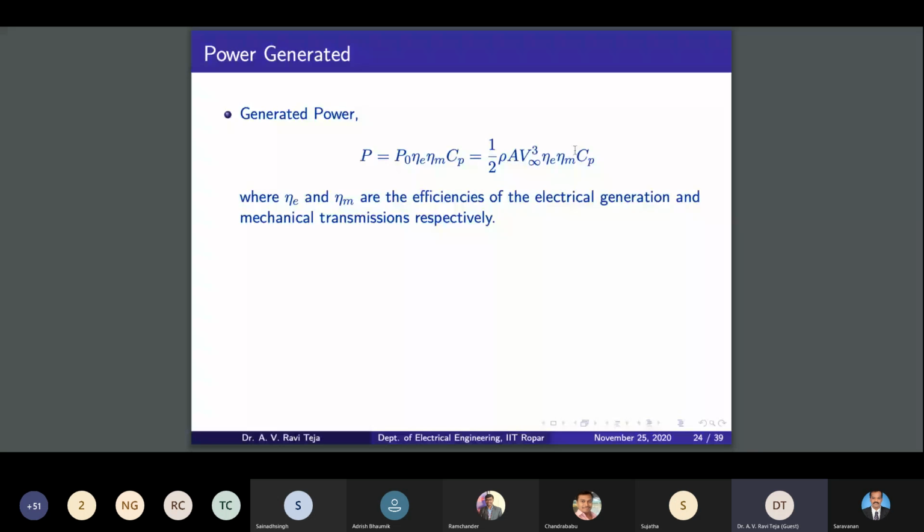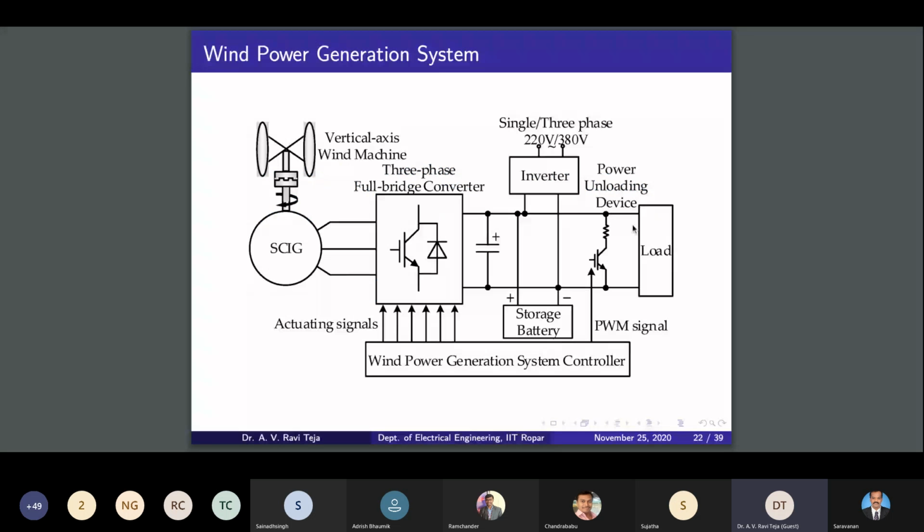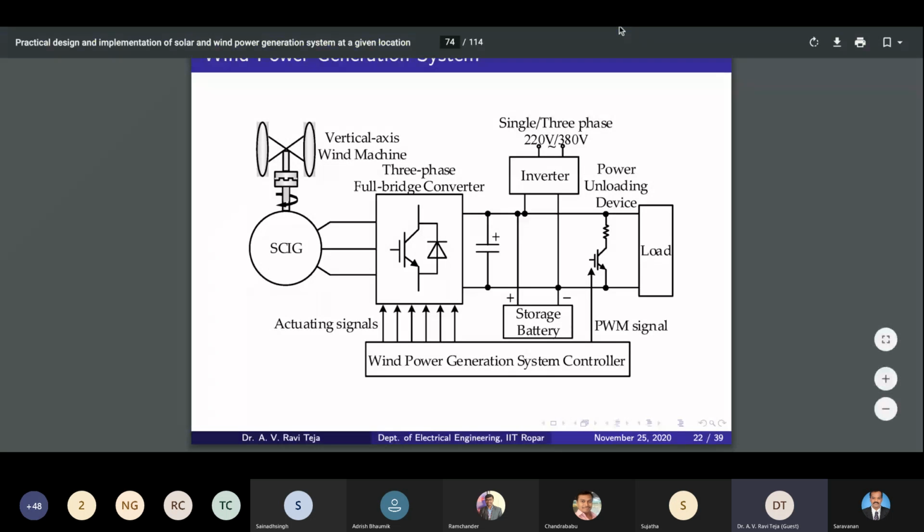And then from this you calculate how much power at the wind turbine stage I have to get in order to give 5 kilowatt, because every component in the system will consume power. So here at the output I am giving 5 kilowatt. So at the turbine output I may have to generate 7 kilowatt, because 2 kilowatt is gone as losses in the entire system. So at this end, how much power do I have to generate? First, that I have to know, because I am going backward, because my requirement comes from the load, not from the other things. So load, I decided I have to give 5 kilowatt. For that, at the turbine I have to generate 7 kilowatt, or say 8 kilowatt, 3 kilowatt is lost in the generator efficiency and other things, gearbox, etc.